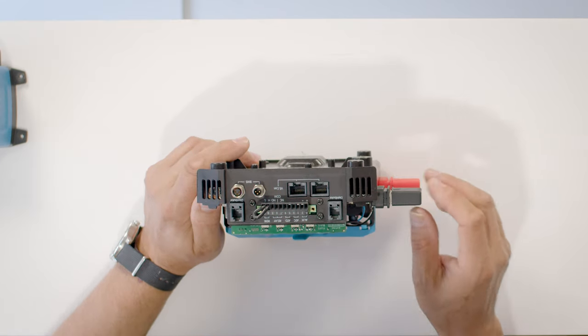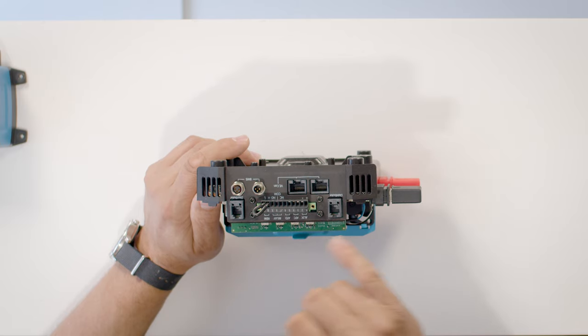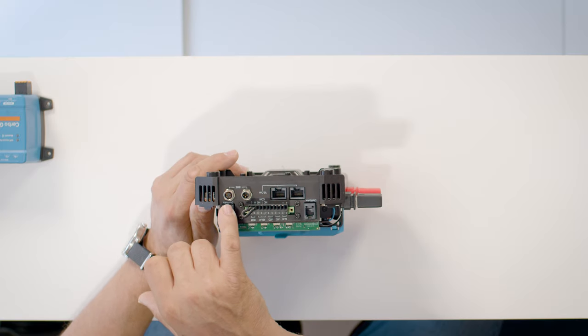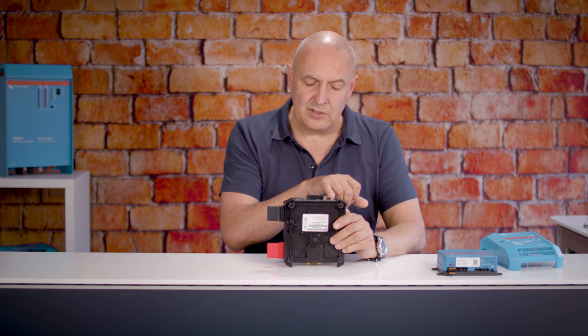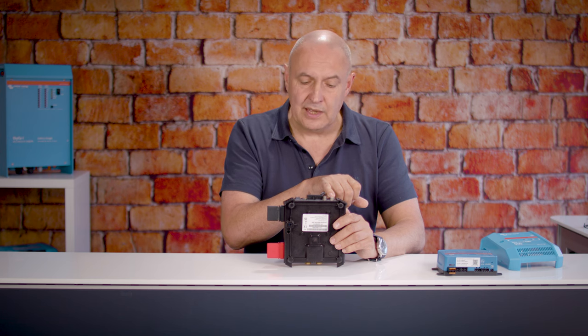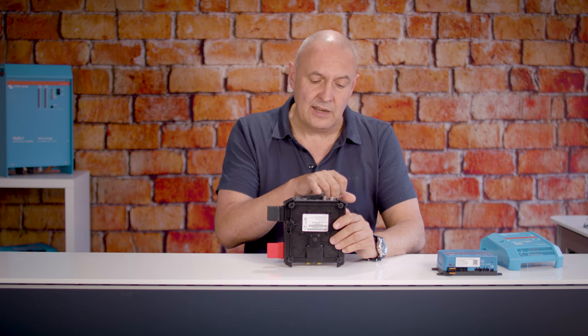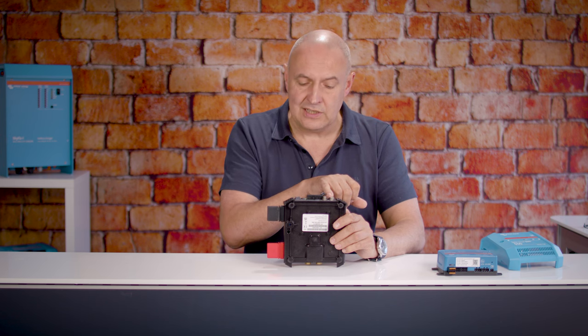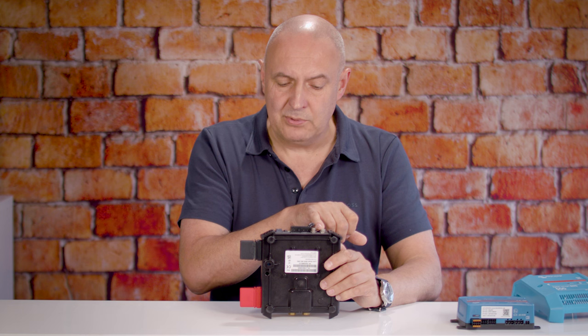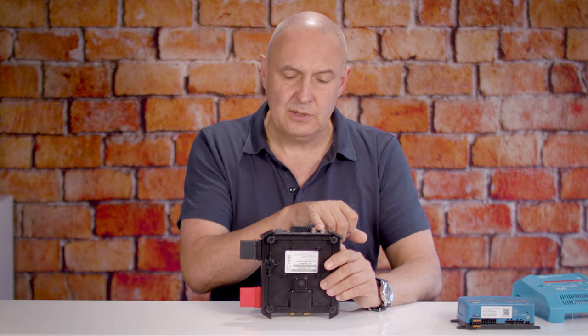And if we have a look at the connection panel, what we can see here is an array of different connections for various devices. So I'm going to walk those through one at a time. These two connectors here are for the BMS cables of the smart batteries. Each smart battery has got an in and an out. You daisy chain them together, and then the two ends of that daisy chain connect into the BMS. These cables allow the batteries to indicate if there is a charging or a discharge issue to the BMS.